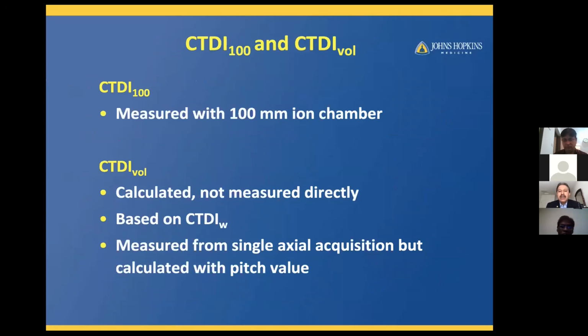Here is some common disclaimer or standard information about the CTDI 100 and CTDI volume. The CTDI 100 is so called because it's measured with a 100 mm ion chamber, and that's standardized across the globe. So if any measurement is given as 100, we know that they used the same phantom and a calibrated ion chamber. From there, we arrive at the CTDI volume, which is calculated, and it is not measured directly. It's measured from a single axial acquisition, but calculated with a pitch value.